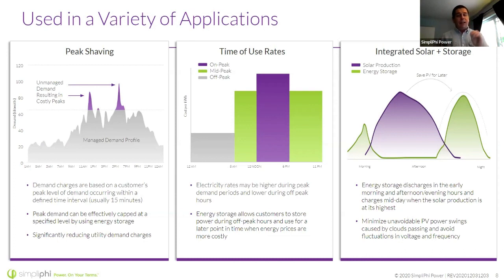A lot of utilities will look at that instantaneous or 15-minute demand and drive your monthly utility bill based on that value. So if you have energy storage, you can program that system to say, I don't want that peak value driving my bill, I want to keep that value low, keep my bill low. And you could program your inverter to say, I don't want to see more than 5 kW pulled from the grid. And if we start to see that demand approaching 5 kW, we can tell our inverter to step up and provide battery power to offset that demand.